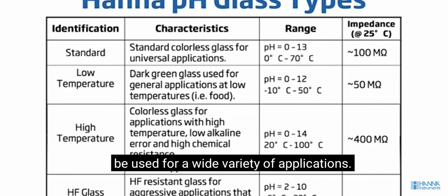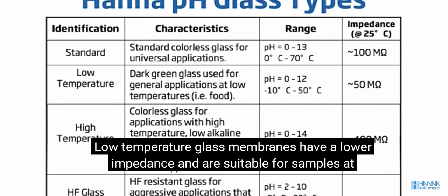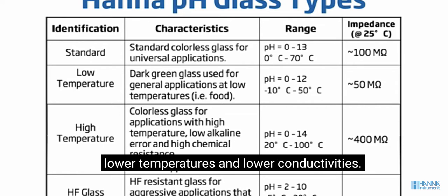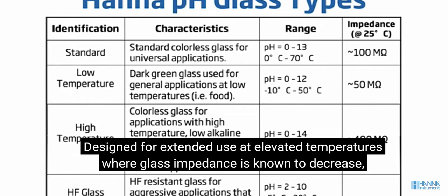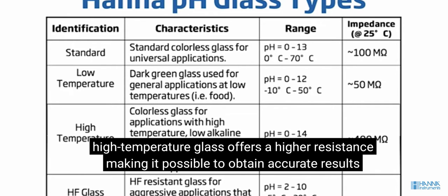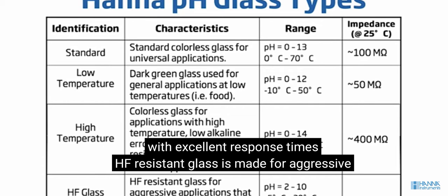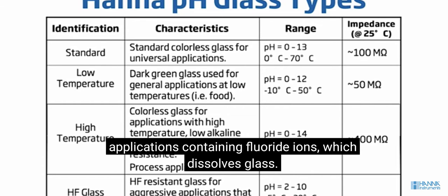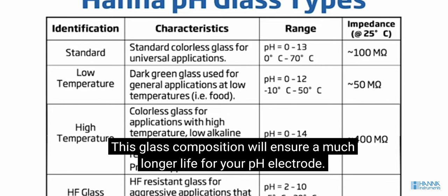of applications. Low temperature glass membranes have a lower impedance and are suitable for samples at lower temperatures and lower conductivities. Designed for extended use at elevated temperatures where glass impedance is known to decrease, high temperature glass offers a higher resistance, making it possible to obtain accurate results with excellent response times. HF-resistant glass is made for aggressive applications containing fluoride ions, which dissolves glass. This glass composition will ensure a much longer life for your pH electrode.